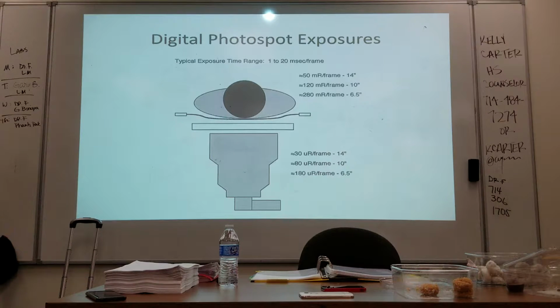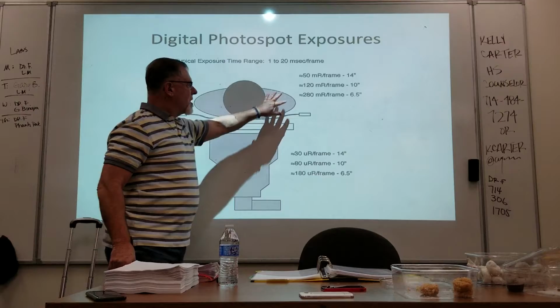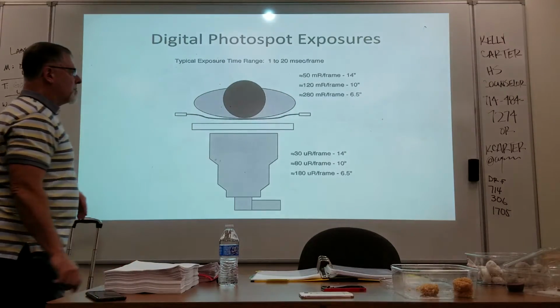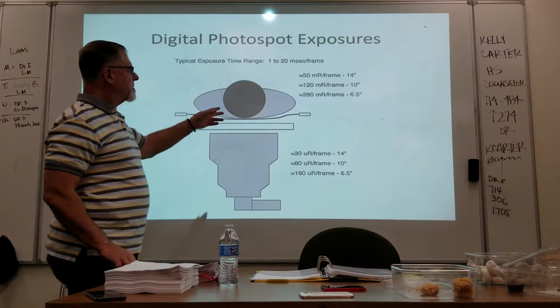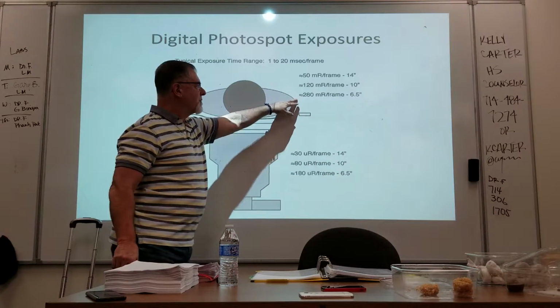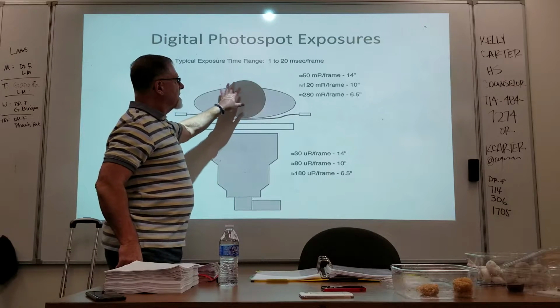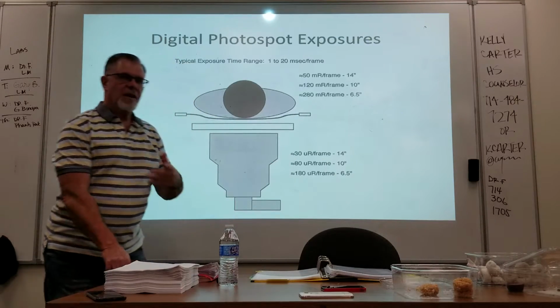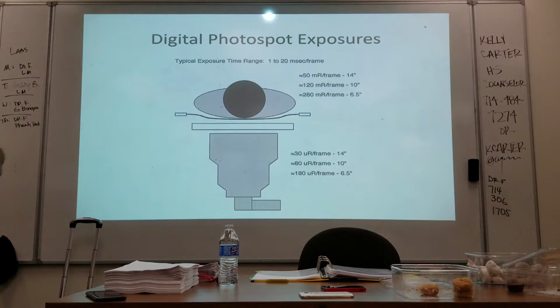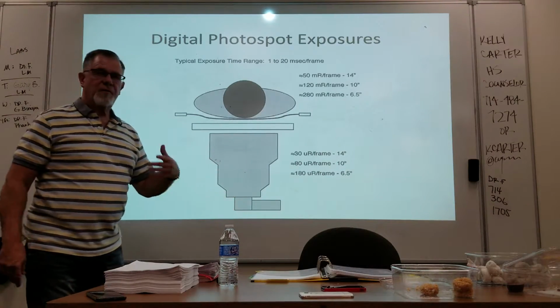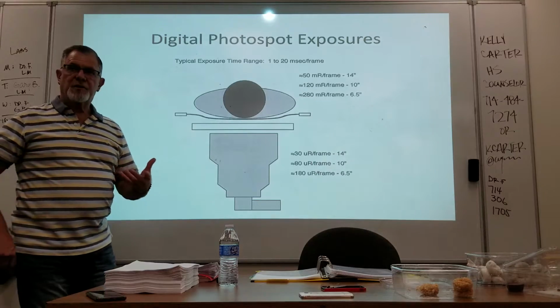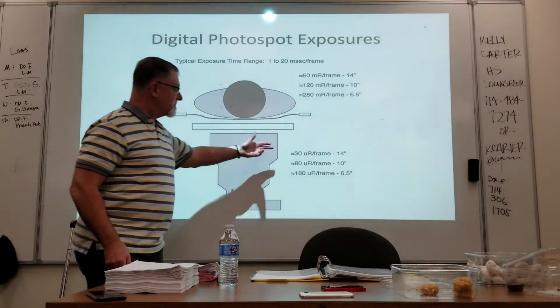Digital photo spot exposures, typical is 1 to 20 milliseconds per frame. Some values that are probably still good, about 50 MR per frame for 14-inch, 120 MR per frame for 10, 260 MR per frame for 6.5. That's what the patient gets, and that's due to the fact that the exposures are based on what the image intensifier needs to see. So the manufacturer sets these up in such a way that the amount of information, the gain, the amount of noise that you get in your images are set. So there's actually specifications for this.